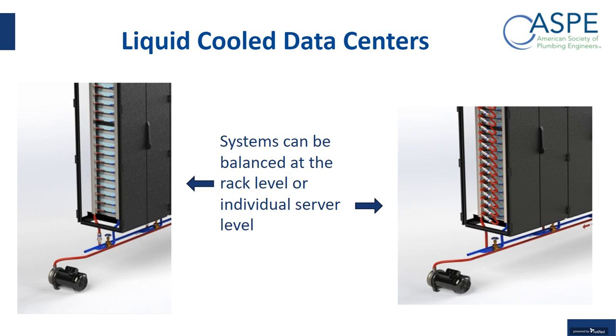So liquid cooled data centers, on the left is a server rack, and all these servers along here have water flowing through them, liquid flowing through them, through a cold plate. And here you're balancing that whole rack to one temperature, which is the least expensive way to do it, but not the best way. A better way and more expensive is you have a thermostatic balancing valve, a cold water balancing valve at each server location. So now if you have one server that's running a lot hotter than another server, that will be individually balanced. So therefore you'll have tighter control over the whole system.